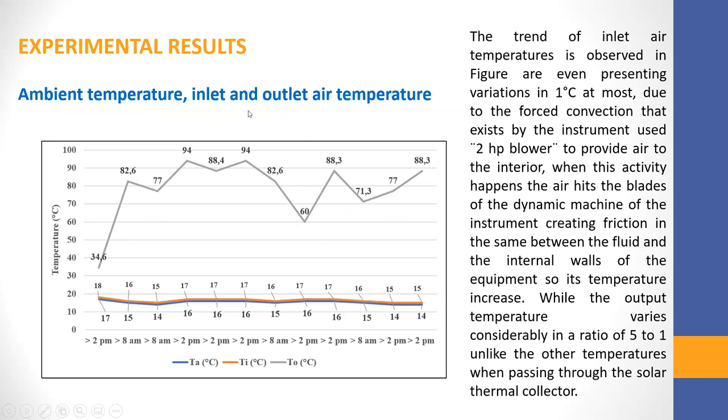Ambient temperature, inlet, and outlet air temperature. The trend of inlet air temperatures is observed in the figure with variations of 1°C at most due to forced convection that exists by the instrument used, the blower, to provide air to the interior. When this activity happens, there is the blade of the dynamic mechanism of the instrument creating friction in the space between the fluids and the internal walls of the equipment, so its temperature increases.